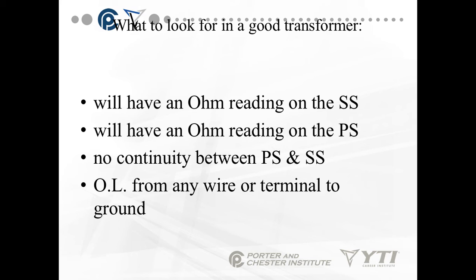Okay, it will have an ohm reading on the secondary side. It will have an ohm reading on the primary side. Notice I'm not giving you any numbers here. And it will have no continuity between the primary and the secondary side.